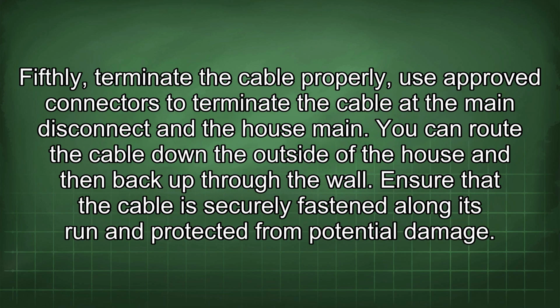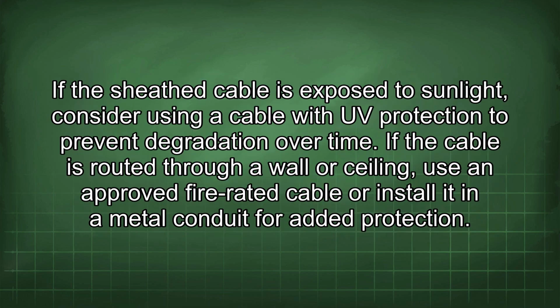Fifthly, terminate the cable properly. Use approved connectors to terminate the cable at the main disconnect and the house main. You can route the cable down the outside of the house and then back up through the wall. Ensure that the cable is securely fastened along its run and protected from potential damage. If the sheathed cable is exposed to sunlight, consider using a cable with UV protection to prevent degradation over time.